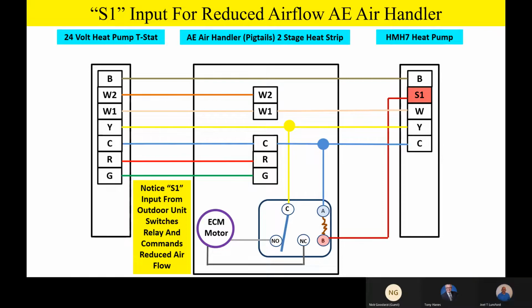Please note also that if we do have a W1 call during that S1 input from the outdoor unit, that airflow reduction input, if we get a W1 call or a heating call, even on straight cooling, if the heat strip comes on as auxiliary heat for some reason, and the outdoor unit is operating in the heating mode, let me take that back, that would be a heat pump only application. But if we do have a reduced airflow and we get an auxiliary heat call for some reason, it's going to ignore that S1 input and drive the fan to 100% heating airflow, or more specifically, whatever high speed tap we selected for heating. So anytime we get an auxiliary heat call, we're going to drive that fan to the high speed.